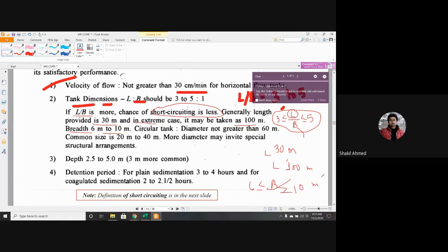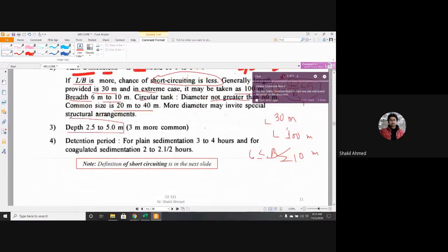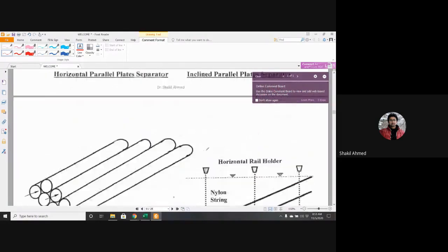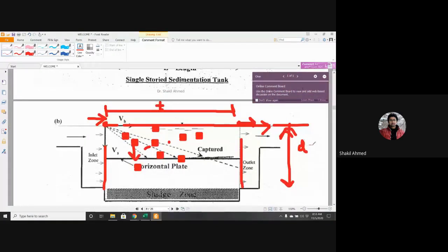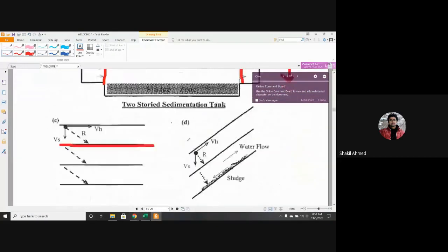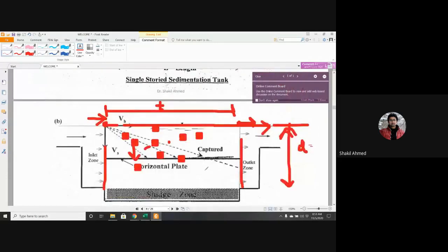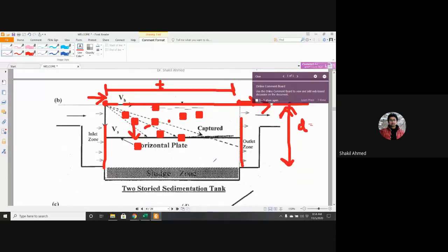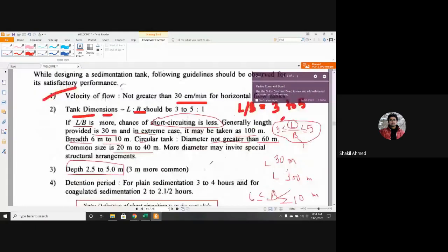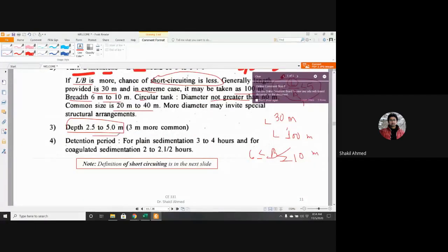Okay. And circular tank diameter should not be greater than 60 meters. Common size is 20 to 40 meters. Depth 2.5 to 5 meters. If you go higher, then it will be difficult to clean the tank. Okay, and there are other problems also. So 2.5 to 5 meters, 3 meters more common. Detention period.